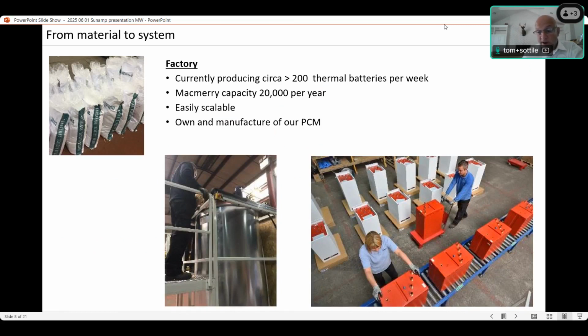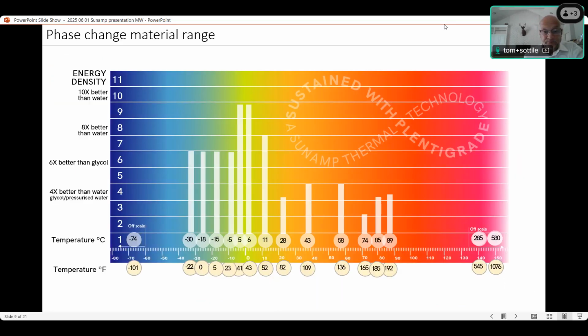You see four pipes coming out of the top of the box. That's two independent heat exchangers that can act as a plate heat exchanger, meaning that we can charge and discharge the battery simultaneously, or we can charge it, store the energy in the phase change material, and then consume it later.